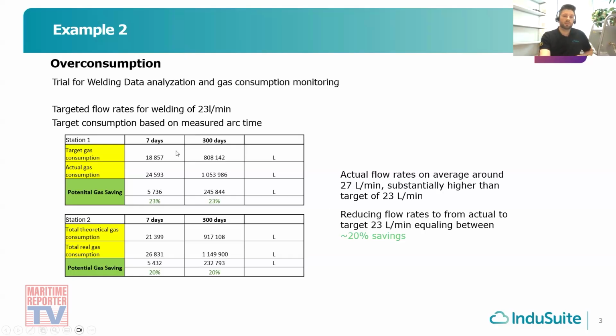There are two different columns, one calculated for 7 days and one for 300 days. On those graphs, you see the target consumption on the left side and the actual consumption, which resulted at the first station in a saving of 23%, and at the second station a savings of roughly 20%—just by reducing the overconsumption measured at roughly 27 liters per minute to the target of 23 liters per minute.